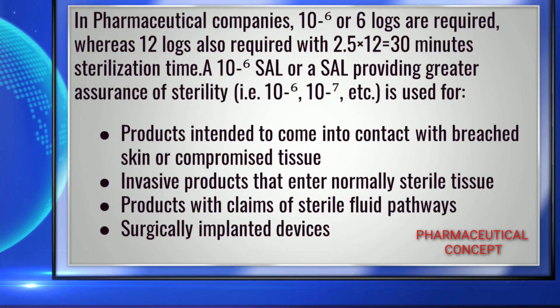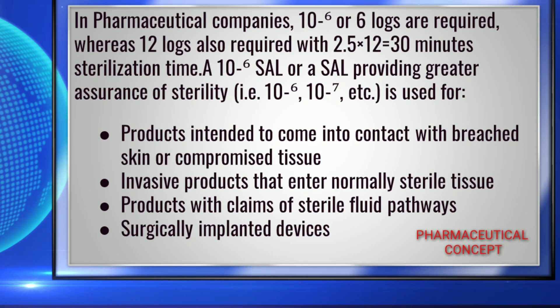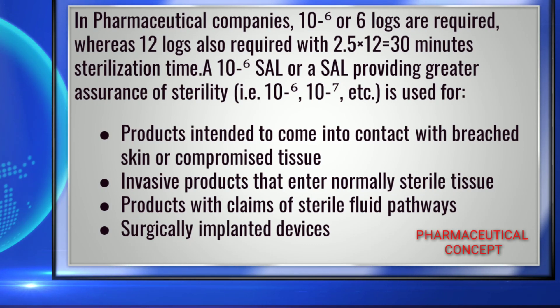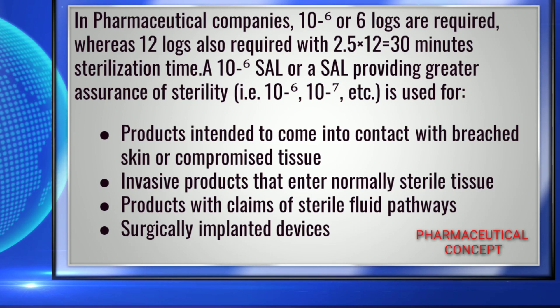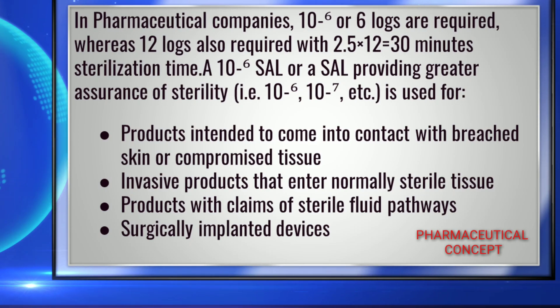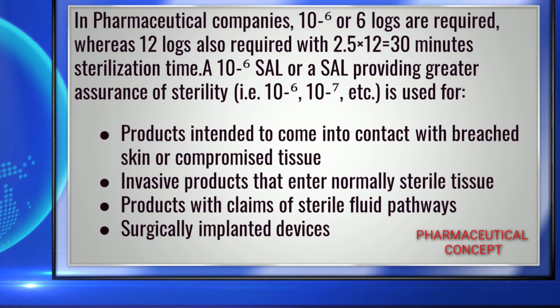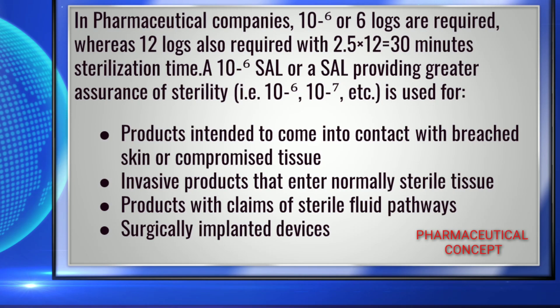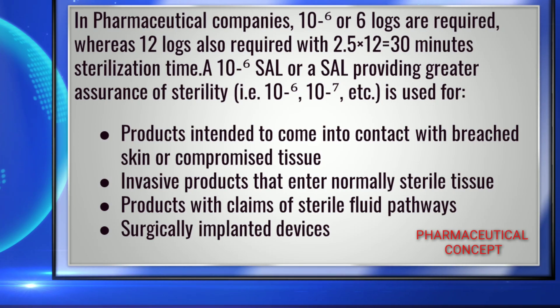In pharmaceutical companies, 10 to the power of minus 6 (6 logs) is required, whereas 12 logs are also required with 2.5 times the sterilization time in certain cases. An SAL of 10 to the power of minus 6 or 10 to the power of minus 7 is used for products intended to come in contact with breached skin, compromised tissue, products that enter normally sterile tissue, products with claims of a sterile fluid pathway, and surgically implanted devices.